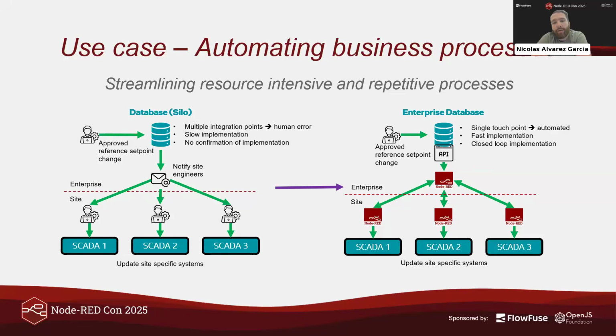Where we're moving to is we want to allow an automated implementation that when that governing body makes a change to those set points, Node-RED basically captures it via the API of the database and pushes it to the different sites accordingly. In the sites, it gets implemented into SCADA via OPC, and there's a confirmation that goes back to the database itself.